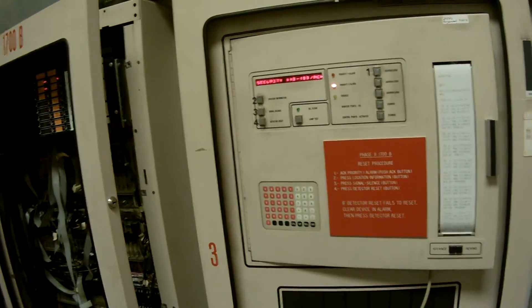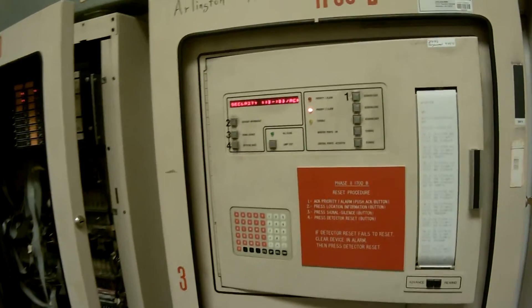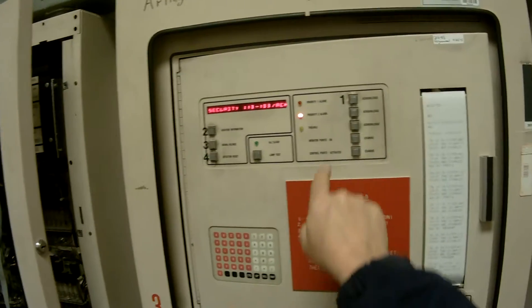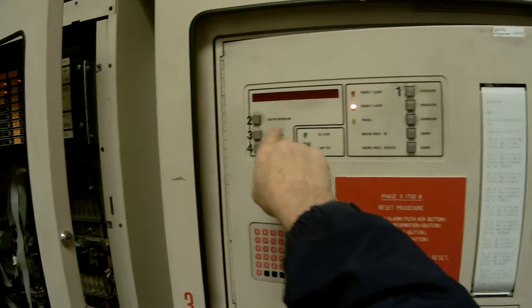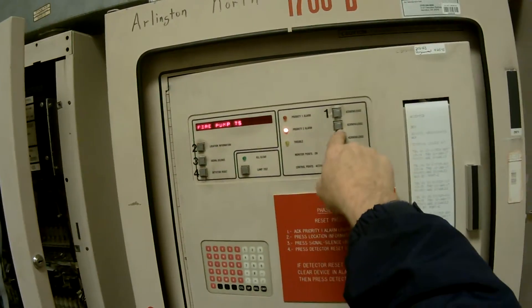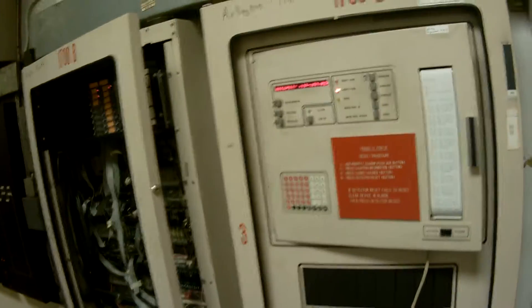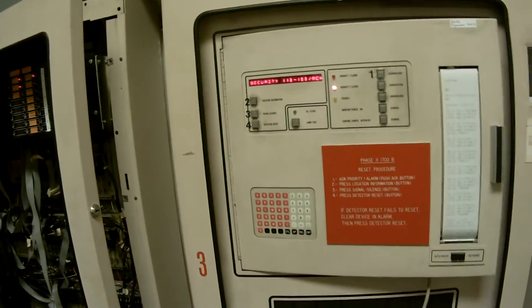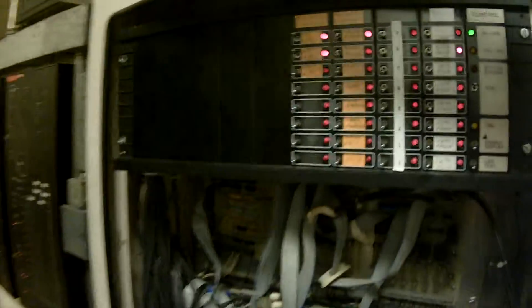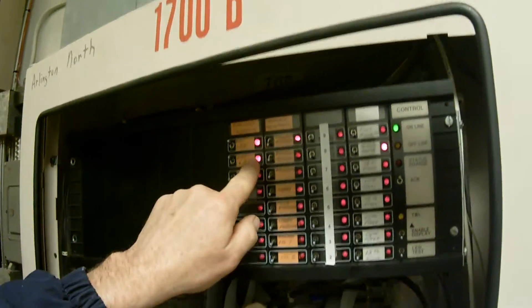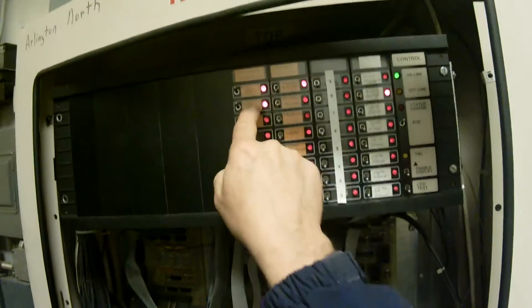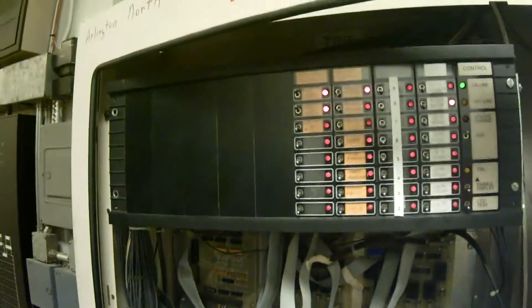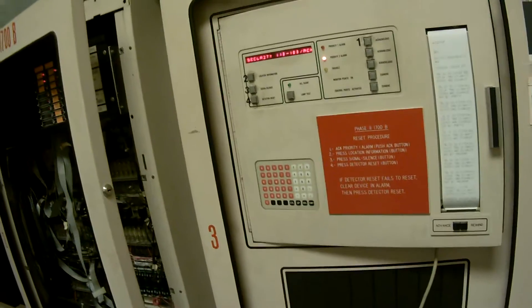One thing is not 100%. Like we said, there's any one thing going on here in this panel, and it's that priority two. So if we could get that tamper switch cleared out, maybe we'll go take a look at that in a little bit. We can get that red light out. And if everything is all clear, and if we go around and we hang all our fire phones up—because that's what all these red lights are, they're fire phones off the hook—if we get them on the hook, more than likely we could get that green light to light up.